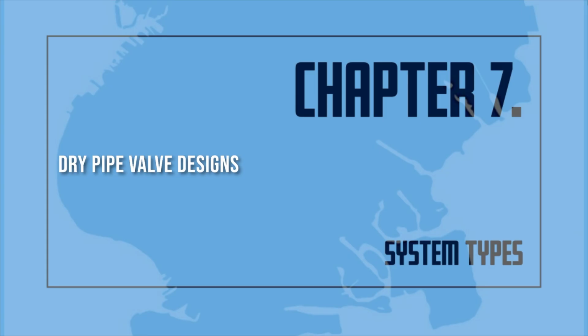Higher than normal water pressure, a water hammer, may cause the dry valve to trip by accident. Water hammer is caused by a sudden flow of water or a sudden change of water pressure in the system. To reduce this danger, air pressure is usually kept well above the normal trip point. The air pressure is usually set at 15 to 20 pounds per square inch above the normal trip level. Some valves are specially designed for low pressures. In all cases, the manufacturer's instructions regarding pressures to be maintained shall be followed.